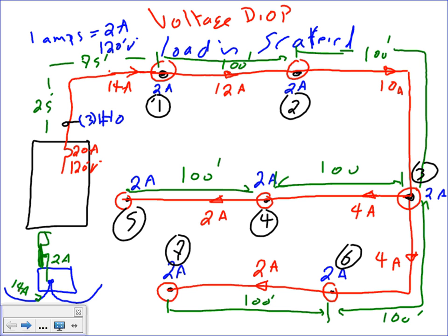Any question about the assumption? Now, you could do the same assumption, guys. Look how easy. If I find that, which one do you think is the worst scenario? The last one. From here to here is 200, and from here to here is 200. These two could be the worst scenario, meaning they might encounter the highest amount of voltage drop.